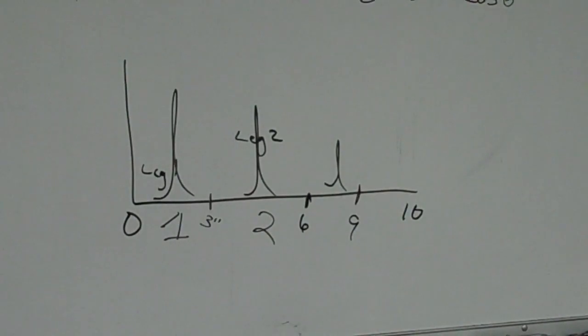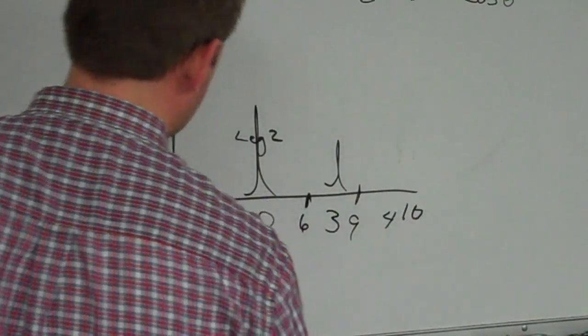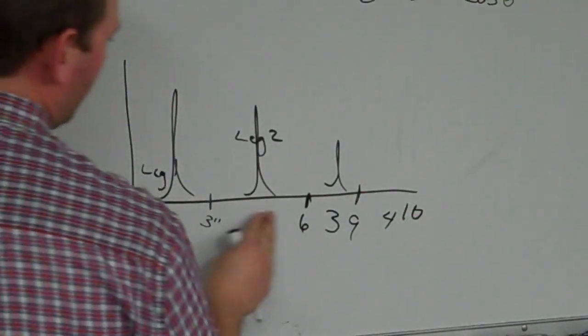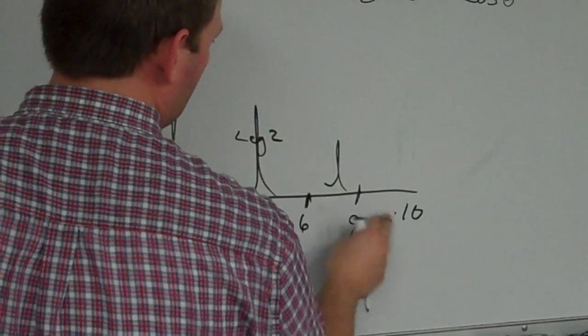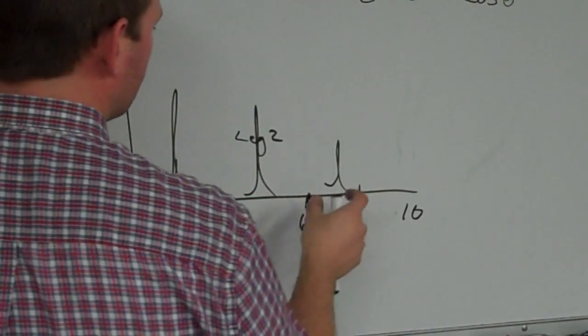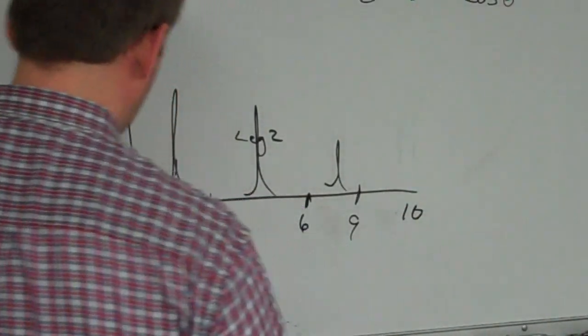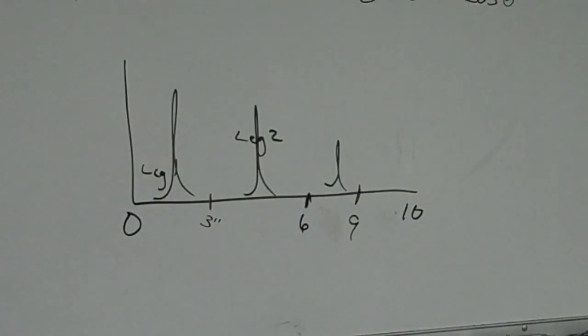At 5.84 inches or roughly 6 inches, that's one V-path. That's where the sound enters, comes back, and bounces. So this would be leg 1 and leg 2. So from 0 to 2.92, meaning roughly 3 inches, this is leg 1 information. So if you have a signal that bounces up in here, you know it's in leg 1. And then if you're going from 3 to 6, you have a signal that bounces up in here, you know you're in leg 2. Then you go from 6 to 9, then you've got leg 3. 9 to 12, so on and so forth, leg 4, leg 5. And some of the scopes, USN 60s and stuff like that, will separate out leg information so you can tell exactly where those defects are coming up. But if you don't have one of those scopes, you need to be aware of on the A-scan from 0 to 3, in this case leg 1, from 3 to 6 leg 2, 6 to 9 leg 3, so on and so forth. And you can do that for any thickness. If your plate's only 375 or 3 eighths of an inch thick, you can calculate that out and would be able to tell exactly on your screen where all that information's coming up. Any questions? Feel free to email me, call me, whatever. We'll get you taken care of and I hope you had a good week.